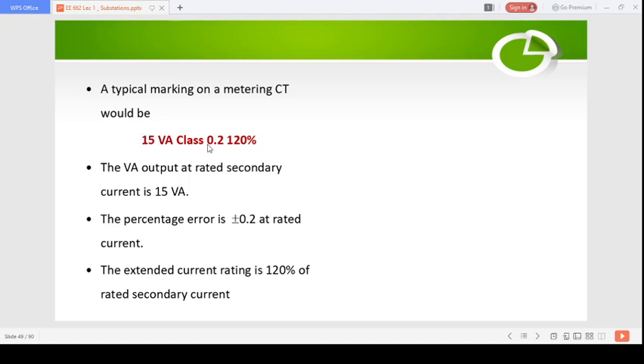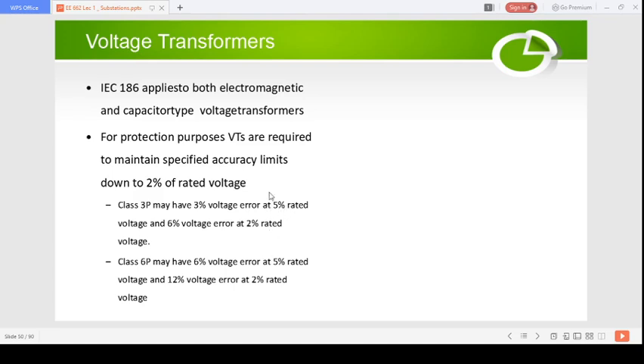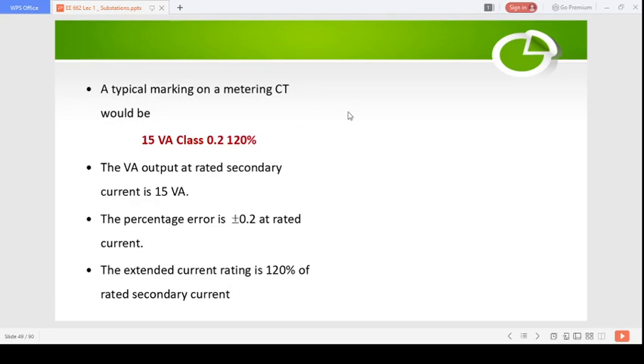So you have 15 VA class 0.2 120%. So the VA output at the rated secondary current is 15 VA, as you have seen in the protective transformers. Then the percentage error is plus or minus 0.2% at the rated current, and the extended current rating is 120% of the rated secondary current. So it can measure up to 120% of the rated secondary current with a good accuracy. Okay, so that's about the current transformers.